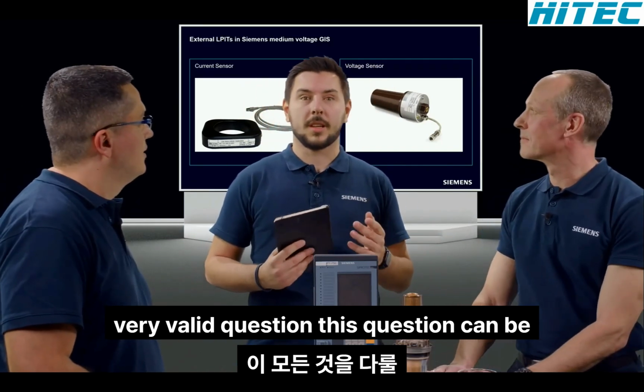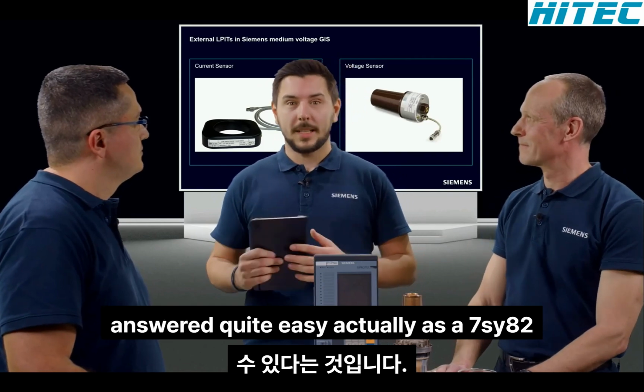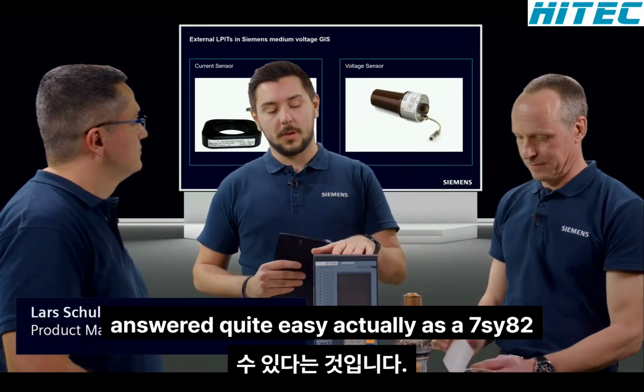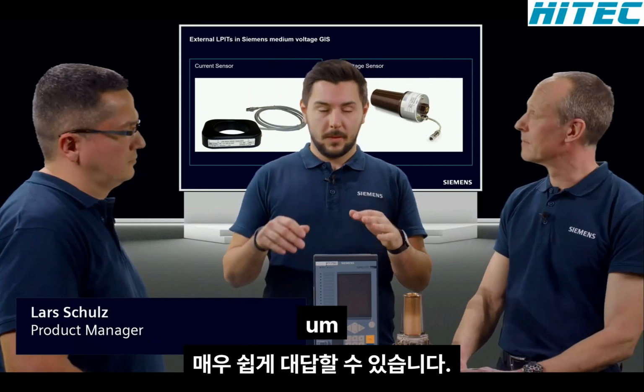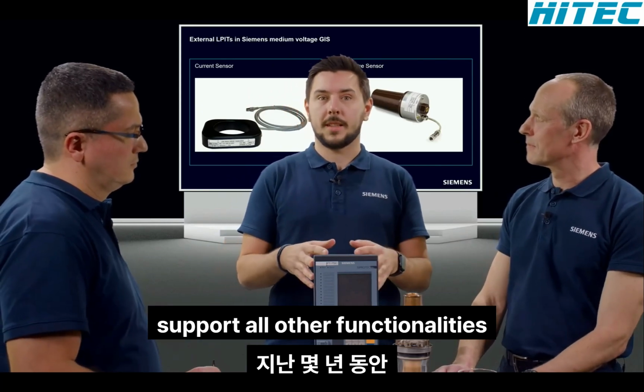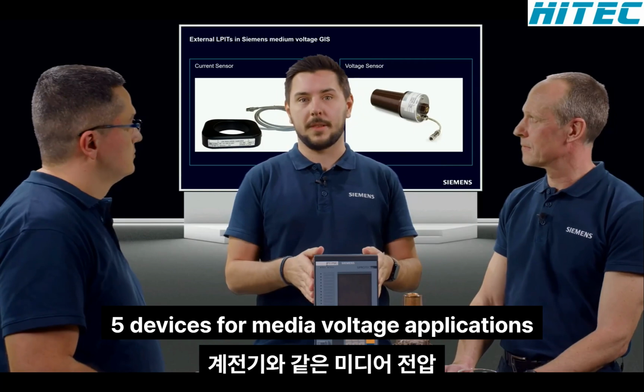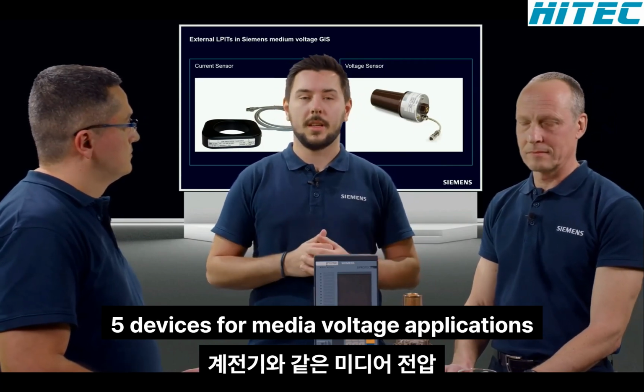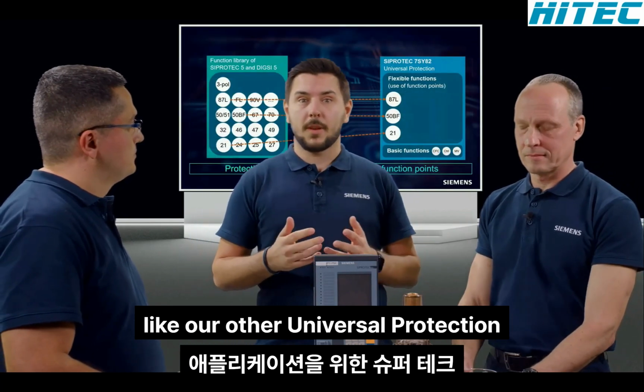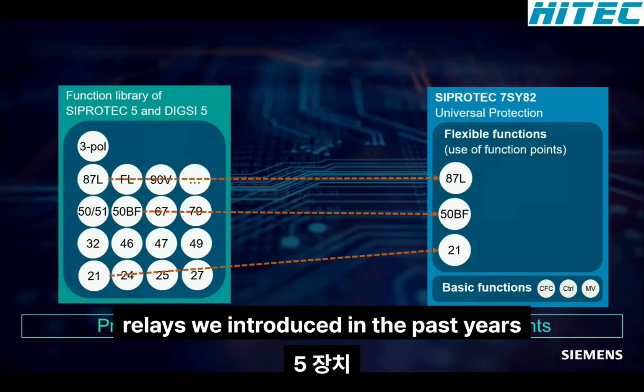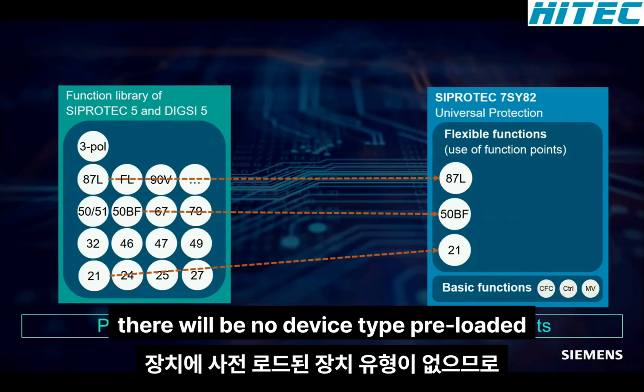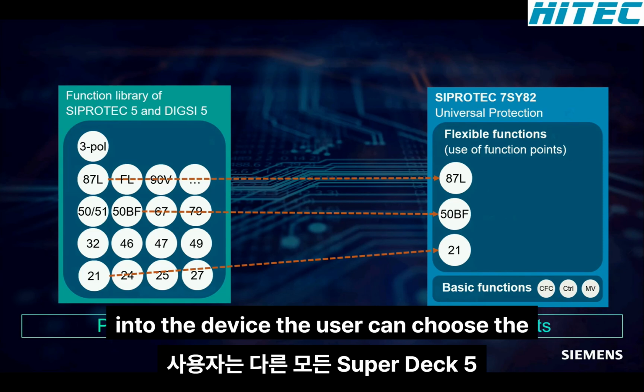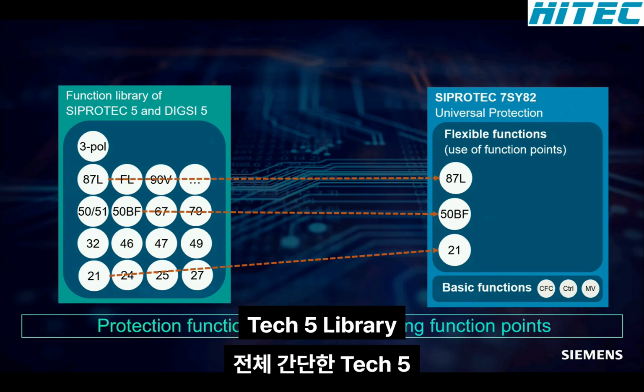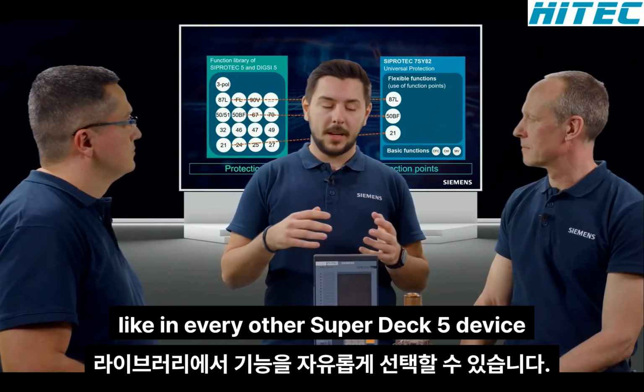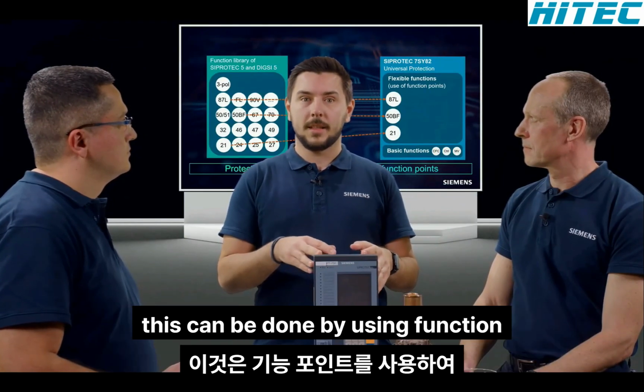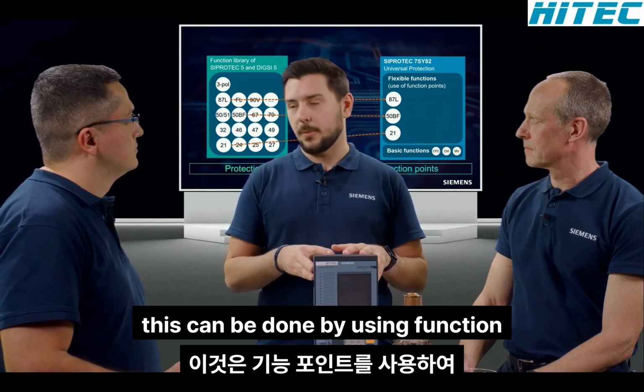That's a very valid question. This question can be answered quite easily, actually, as the 7SY82 will also be able to support all other functionalities available in the other known SIPROTEC 5 devices for medium voltage applications. Like our other universal protection relays we introduced in the past years, there will be no device type preloaded into the device. The user can choose the functions freely from the whole SIPROTEC 5 library. Like in every other SIPROTEC 5 device, this can be done by using function points.